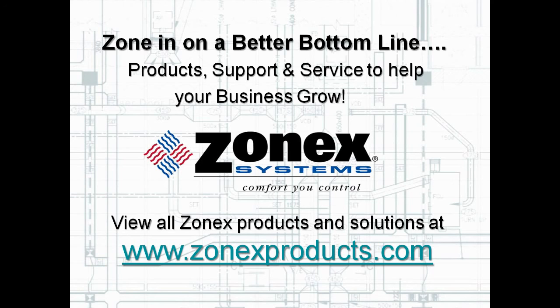And if you have an older control system, like an old Parker or Carrier VVT, OmniZone, Trane VariTrac, York Easy Zone, or other older zoning system, the Gen 3 is the easiest solution to retrofit and upgrade any system using the existing dampers, saving the contractor a ton of money and time, pulling out the old boxes, buying new dampers, coupled with the reinstallation time and cost. Gen 3 is a great choice for new VVT installations, or a great, easy, low-cost solution to upgrade older, outdated, or marginally performing VVT-type systems.